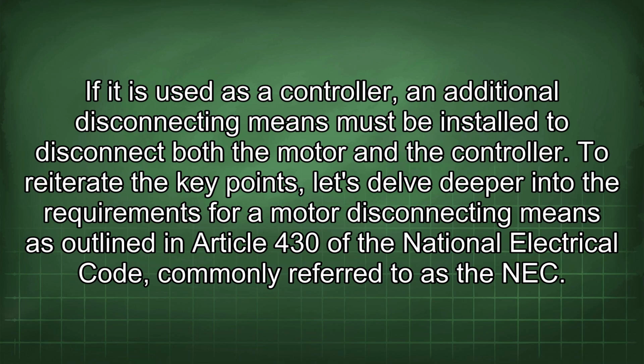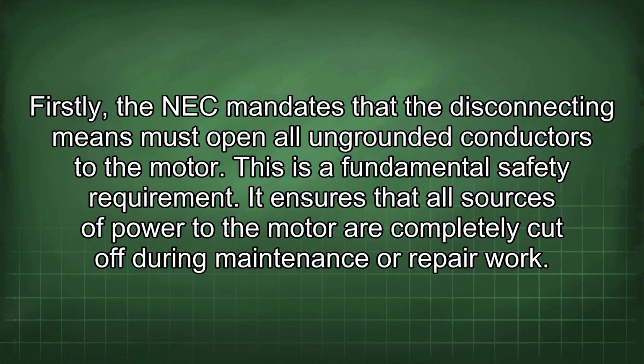To reiterate the key points, let's delve deeper into the requirements for a motor disconnecting means as outlined in Article 430 of the National Electrical Code, commonly referred to as the NEC. Firstly, the NEC mandates that the disconnecting means must open all ungrounded conductors to the motor. This is a fundamental safety requirement. It ensures that all sources of power to the motor are completely cut off during maintenance or repair work.